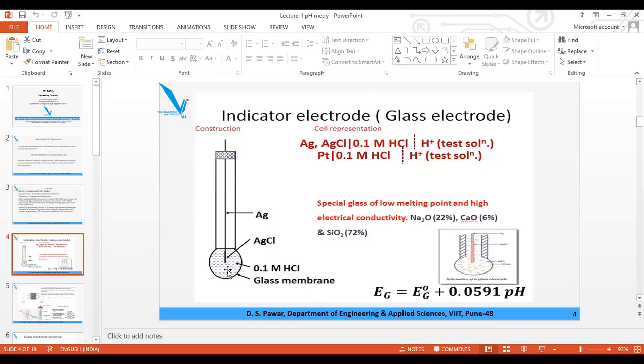Here 0.1 molar HCl is there. This is a glass membrane which is ion selective, which can determine the concentration of any desired ion in presence of n number of ions. Here we are using the pH metric for H plus ions. So if H plus ions are there and in the outer solution HCl is there, then H plus and Cl minus, two types of ions are there, but it can determine the concentration of H plus only. That is the condition because it is an ion selective electrode. So the Ag AgCl electrode is sealed in the cap, or sometimes platinum is sealed in it.